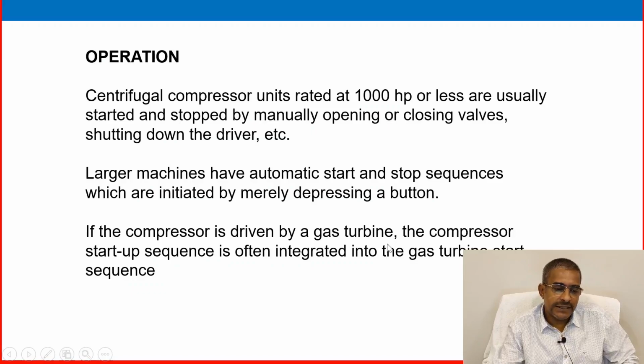Next is operation. Centrifugal compressor units rated at 1000 HP or less are usually started and stopped by manually opening and closing the valves, shutting down the driver, etc. Large machines have automatic start-stop sequences which are initiated by merely depressing a button. If the compressor is driven by a gas turbine, the compressor startup sequence is often integrated into the gas turbine start sequence. Definitely it is interconnected or interlocked with the driving means, the driver system.